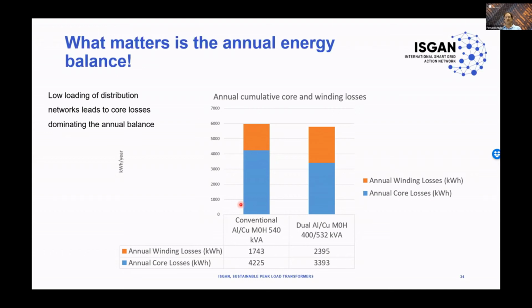So a reduction in size leads to lower core losses, as we can see here. Of course, such reduction in size leads to higher winding losses here. But overall, what we can see is that the reduction in core losses is bigger than the increase in winding losses. So on an annual basis, the energy performance remains equal or slightly improved. And this is actually what matters: how much absolute energy is consumed, not theoretical points on the transformer.